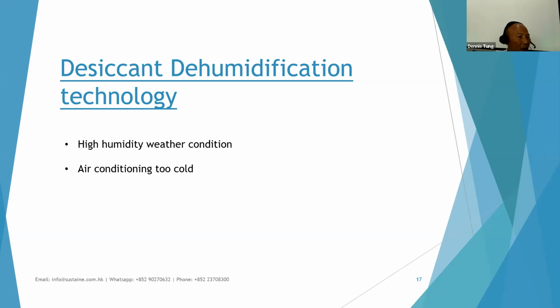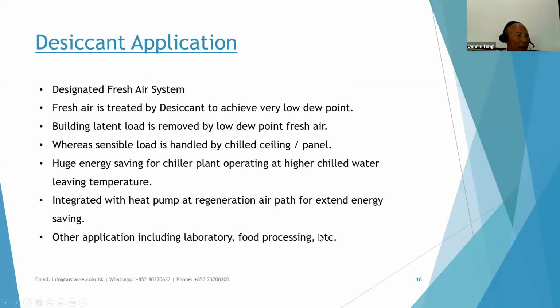However, the temperature will be too cold. The air conditioning will be too cold, and people need to put more clothes on, or use some method to reheat the air to meet the comfort level. Another system which is very famous all over the world is the dedicated fresh air system. A dedicated fresh air system treats the latent load and the sensible load of a building separately.